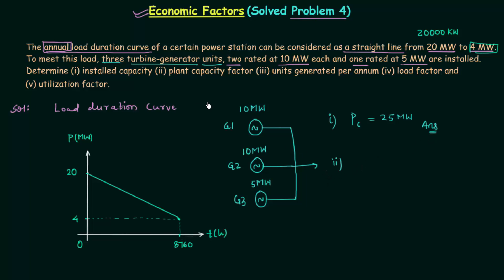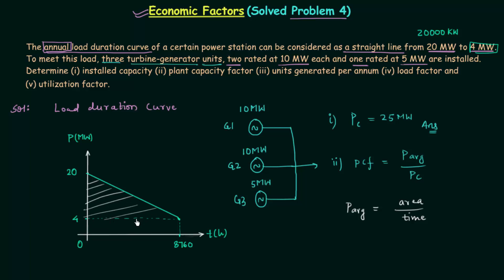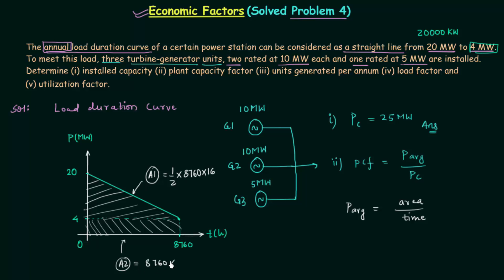In the second part, we need to calculate the plant capacity factor (PCF), which equals average power divided by installed capacity. We calculate average power using the load duration curve: average power = total area under the curve divided by total time. The total area is split into a triangle (A1) and a rectangle (A2). Area A1 = ½ × 8760 × (20 − 4) = ½ × 8760 × 16. Area A2 = 8760 × 4.